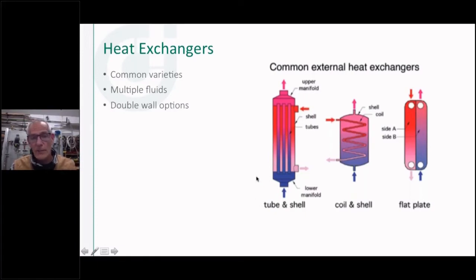I might use this for making domestic hot water. I might have a snow melt that I want to put glycol in. I want to run the boiler on regular water. I might use a heat exchanger like this. You can move a lot of energy through these little plate heat exchangers over here in these different types of heat exchangers. So sometimes you'll see a coil right in the side of a boiler, a tankless coil, just a cage of copper tube that goes in the side of that. It's just basically a heat exchanger that's using the boiler fluid on one side, and the domestic water goes through the inside of that.